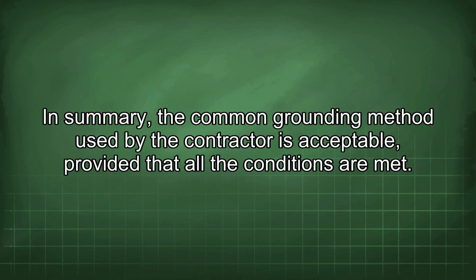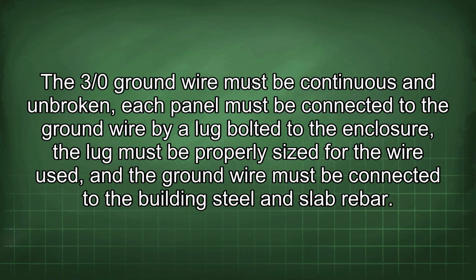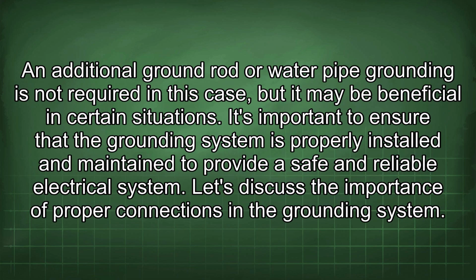In summary, the common grounding method used by the contractor is acceptable, provided that all the conditions are met. The 3/0 ground wire must be continuous and unbroken. Each panel must be connected to the ground wire by a lug bolted to the enclosure. The lug must be properly sized for the wire used, and the ground wire must be connected to the building steel and rebar. An additional ground rod or water pipe grounding is not required in this case, but it may be beneficial in certain situations.